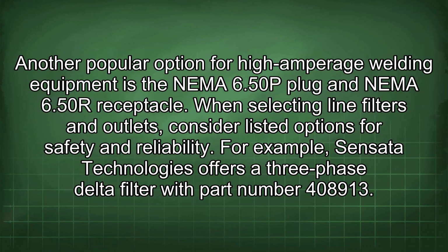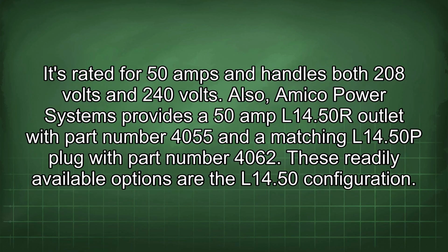For example, Sensata Technologies offers a three-phase delta filter with part number 408913. It's rated for 50 amps and handles both 208 volts and 240 volts. Also, Amico Power Systems provides a 50 amp L14-50R outlet with part number 4055 and a matching L14-50P plug with part number 4062. These readily available options are the L14-50 configuration.